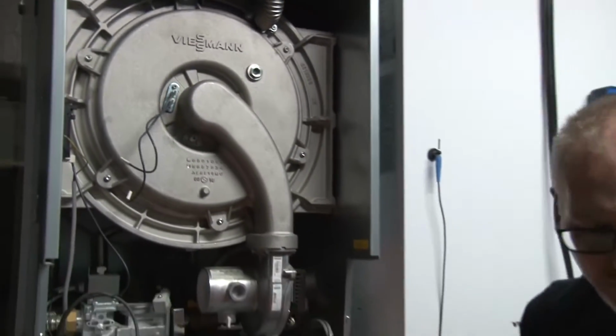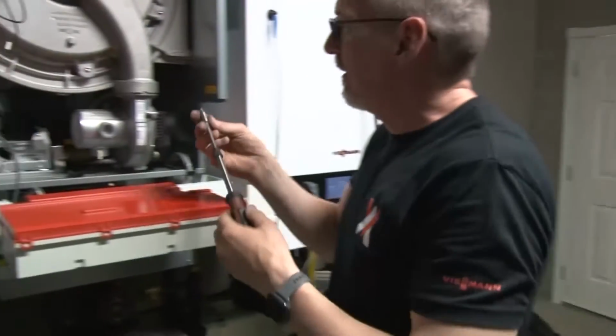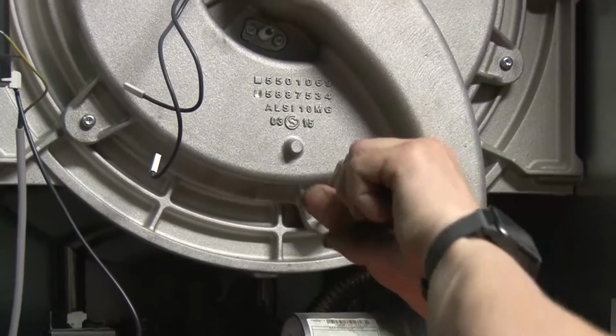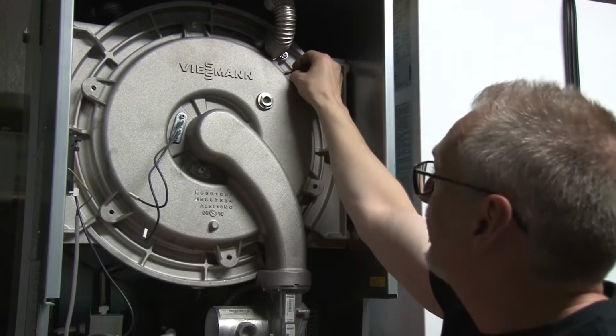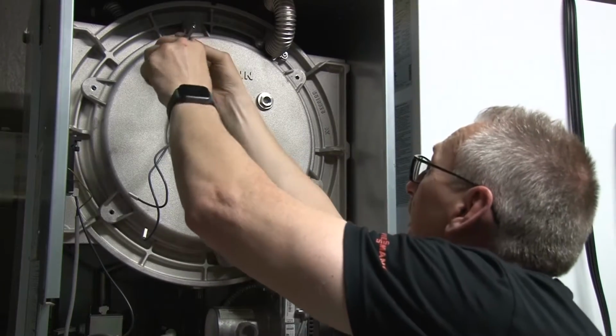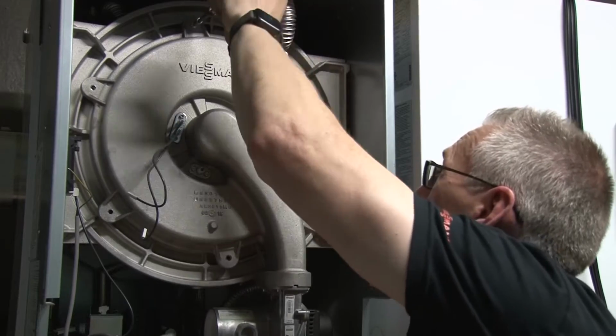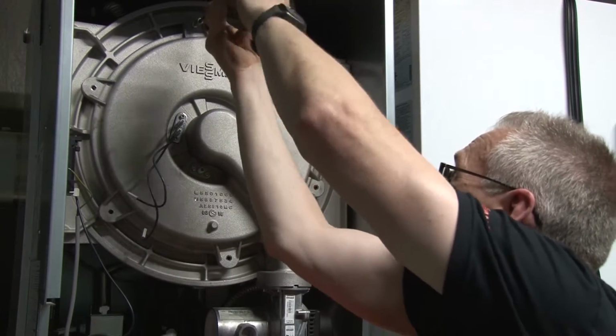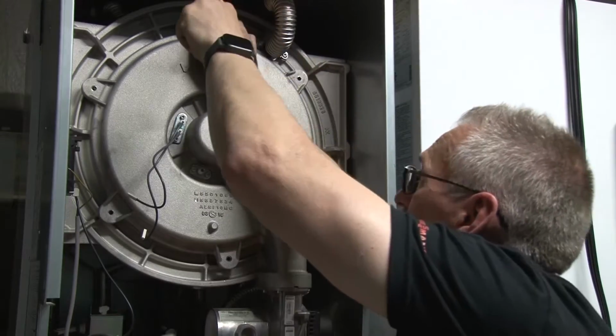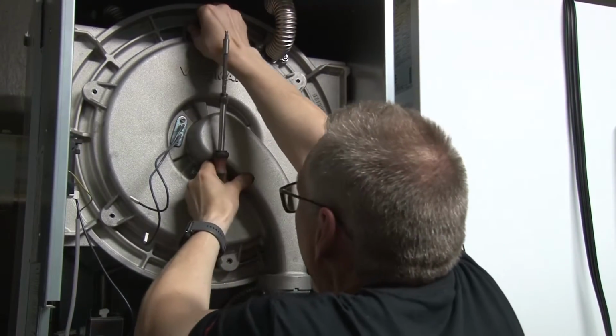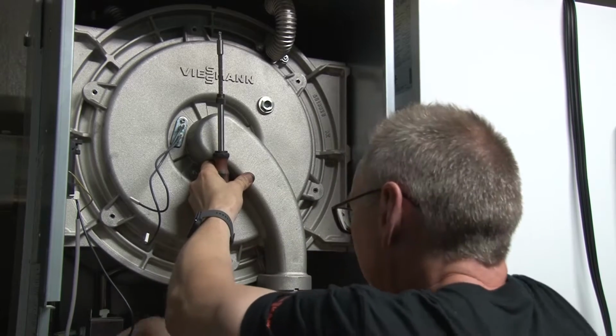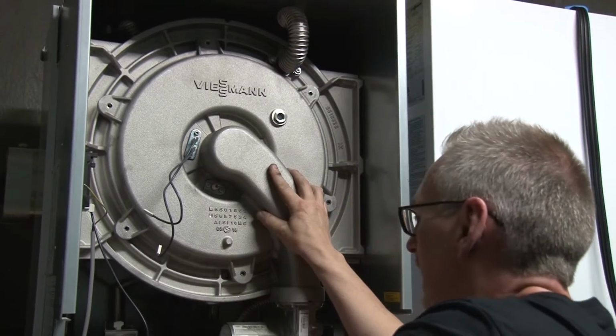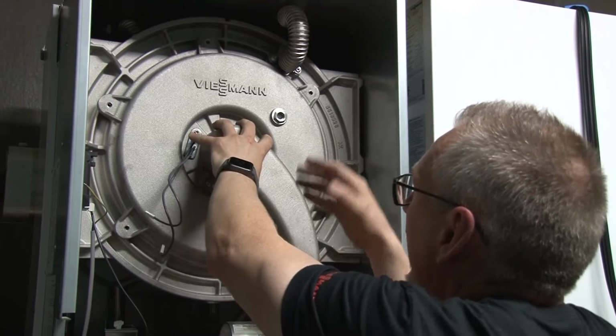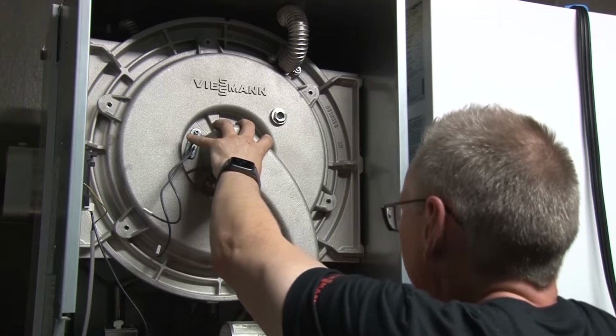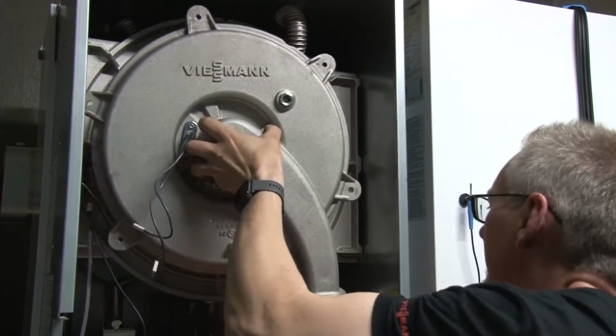There we go. So those are out, and I'm going to show you how to measure that gap and distance when we take the burner out. That's a Torx bit, and it's important to have the right tools for the job when you're doing this. All right, so we'll pull this out. It's a bit of a tall boiler room as far as where the boilers are hung. It's for maintenance of the system that they put the boilers up at this height, but you would want to get up a ladder. We're going to have to get up a ladder to do the combustion test, but I should be able to pull this out fairly easily.